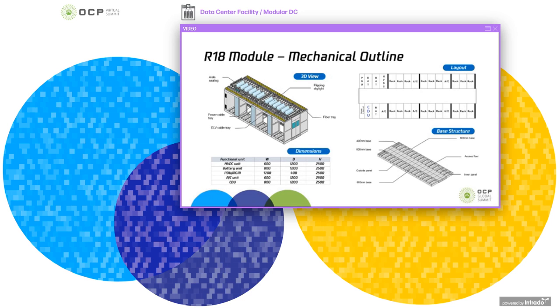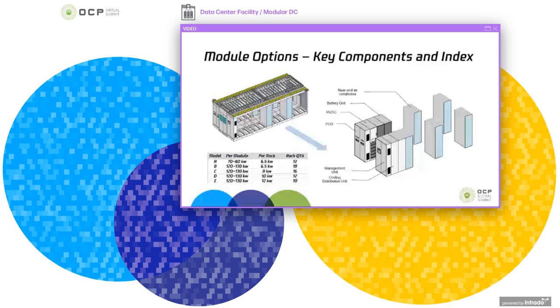The detailed layout of the base structure is on the right hand side, and you could also refer to our online documentation for more details. We offer and have validated 5 models of TMDC, offering different cooling capacity and IT volume, up to 120 kilowatt to 130 kilowatt power capacity per module, and the per rack budget varies by the rack quantity. Be aware, the cooling capacity is the key point. Actually, the power capacity is not a limitation. If you would like more information about the cooling and those parameters, you could go to the OCP portal and find our specifications there.